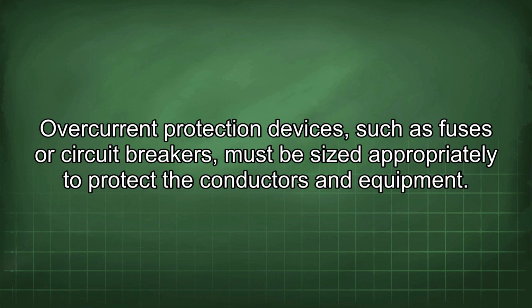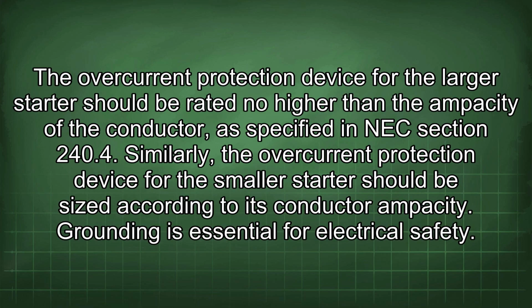Overcurrent protection devices, such as fuses or circuit breakers, must be sized appropriately to protect the conductors and equipment. The overcurrent protection device for the larger starter should be rated no higher than the ampacity of the conductor as specified in NEC section 240.4. Similarly, the overcurrent protection device for the smaller starter should be sized according to its conductor ampacity.